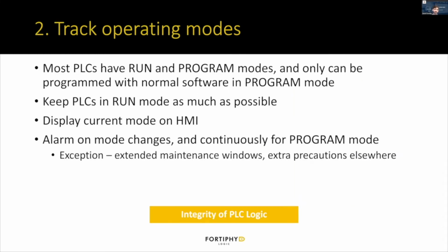The next practice is track operating modes. So most PLCs have run and program modes, and they can only be programmed with the normal engineering software while they are in the program mode. So the general recommendations here are keep PLCs in run mode as much as possible, because if they're left in program mode, that just makes it way easier for attackers to reprogram them and cause problems.